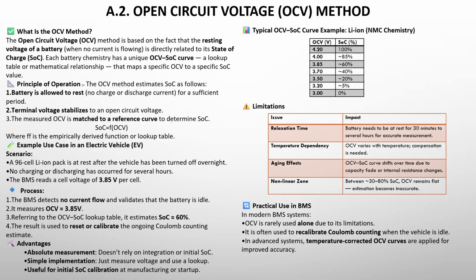SOC as a function of OCV—like taking its temperature when it's calm. Good analogy. So if a 96-cell EV pack rests overnight and the BMS measures a stable 3.85 volts per cell, it checks its lookup table, maybe adjusted for temperature, and finds that corresponds to, say, 60% SOC. This reading is gold for recalibrating the Coulomb counter—it gives it a known, accurate starting point again.